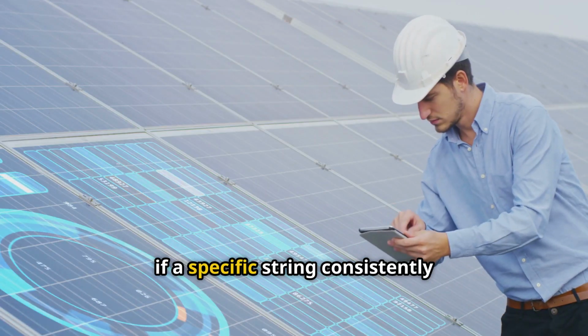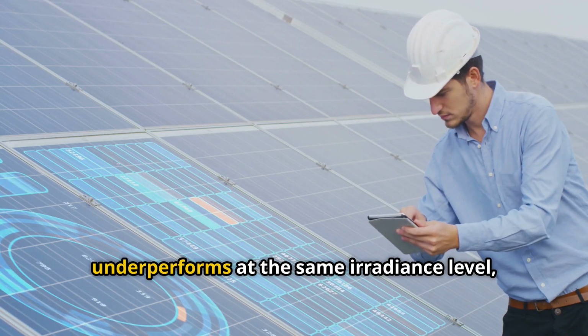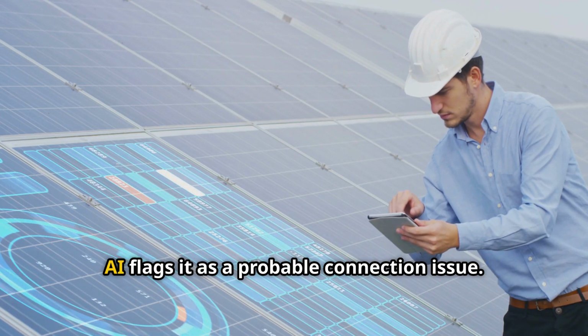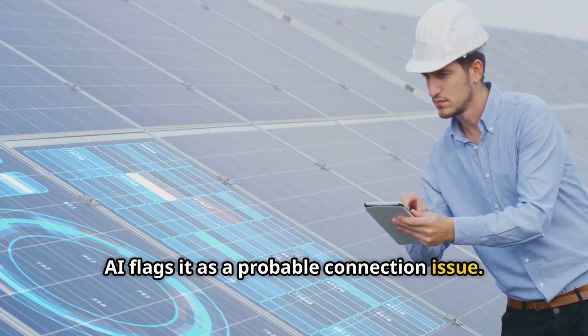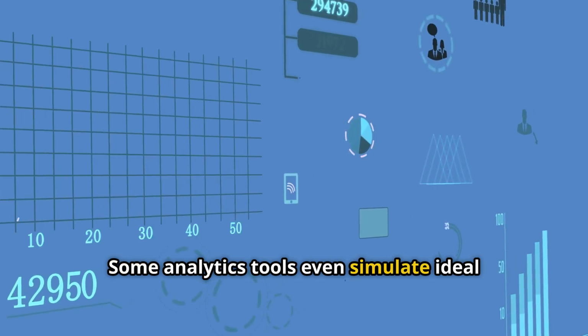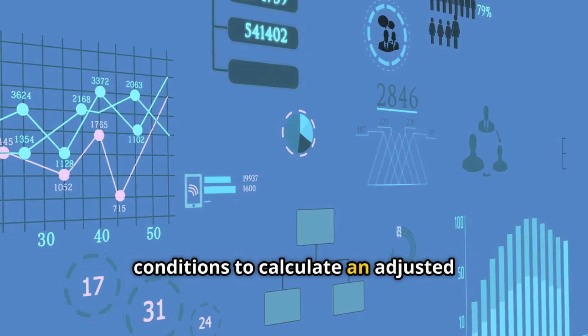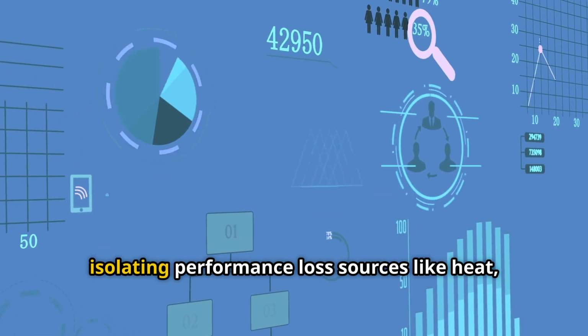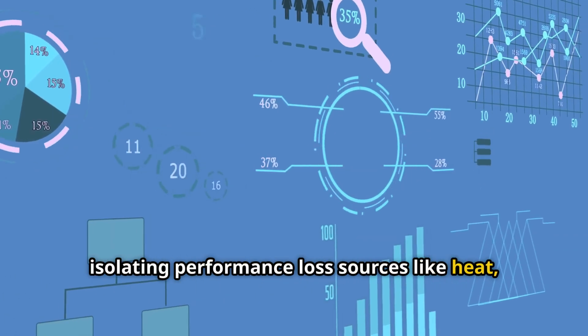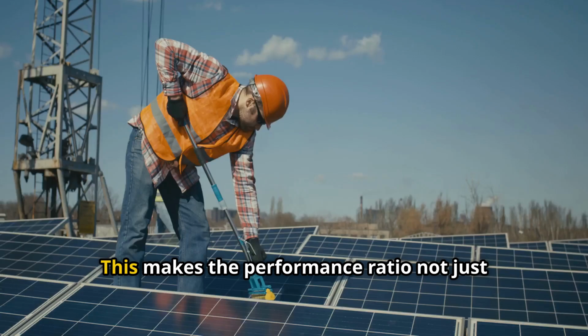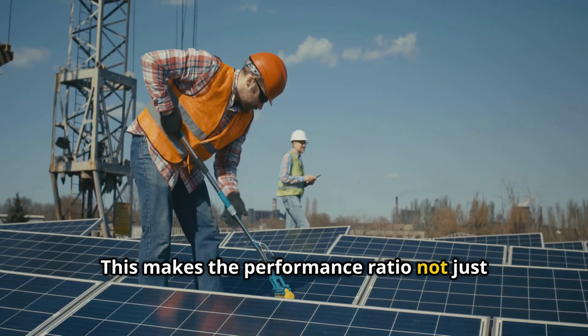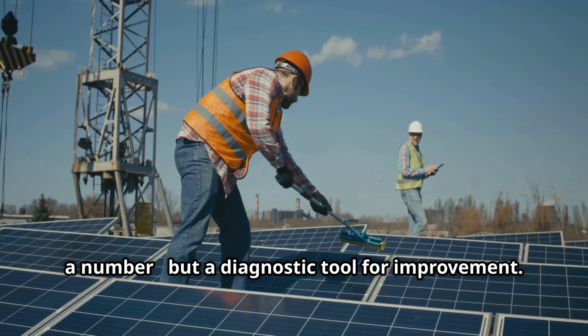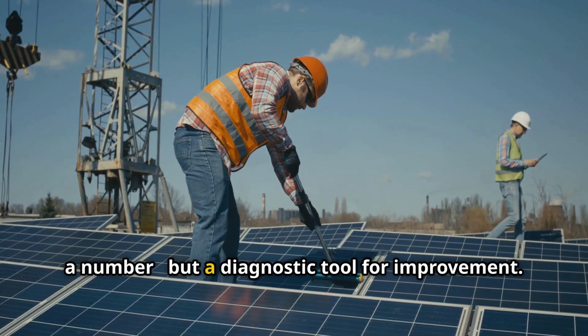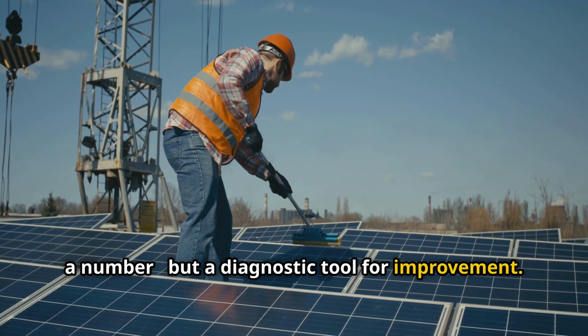For example, if a specific string consistently underperforms at the same irradiance level, AI flags it as a probable connection issue. Some analytics tools even simulate ideal conditions to calculate an adjusted performance ratio, isolating performance loss sources like heat, soiling, or inverter clipping. This makes the performance ratio not just a number, but a diagnostic tool for improvement.